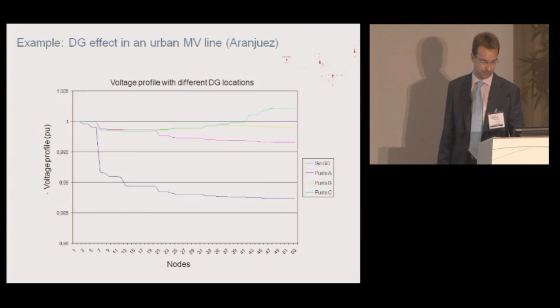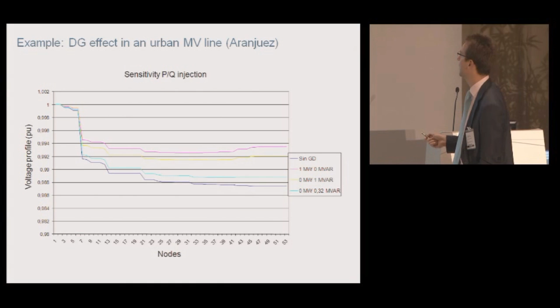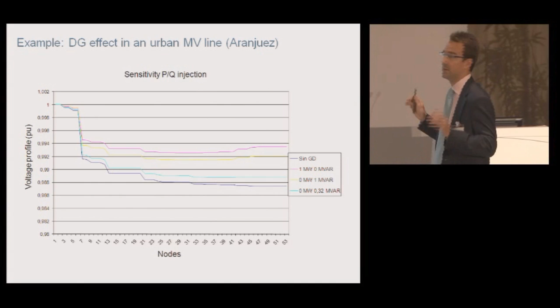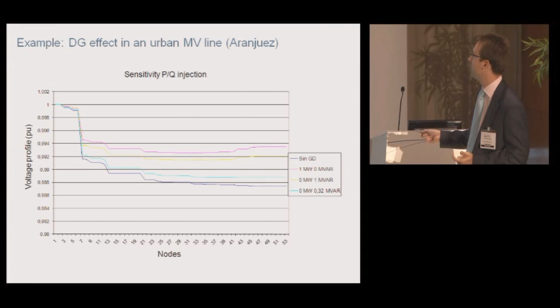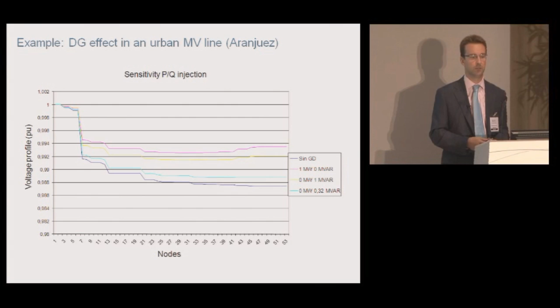And also, remember, we said before that active power is a much more important driver for voltage control in medium voltage than reactive power. And here you have the graph. This is the curve with no distributed generation connecting into the grid. And this red, or magenta, one is the one when we are injecting only 1 megawatt with no reactive power. What is the biggest variation that we are finding? If we are injecting no active power and 1 megavar of reactive power, the variation is going to be less than the one with active power. So here it is demonstrated that active power is a more significant driver than reactive power.